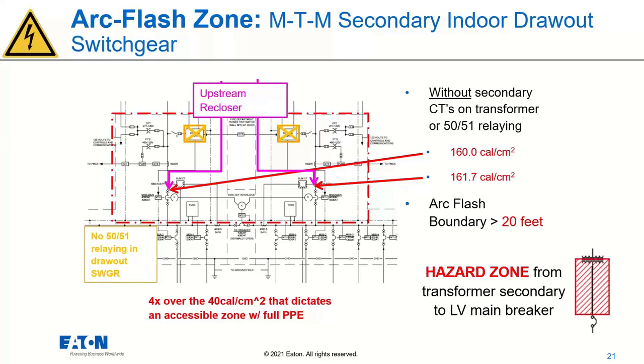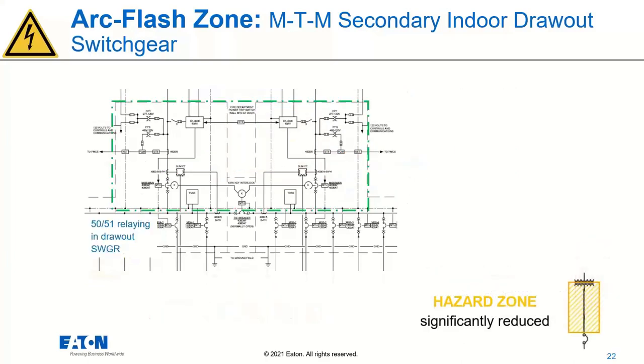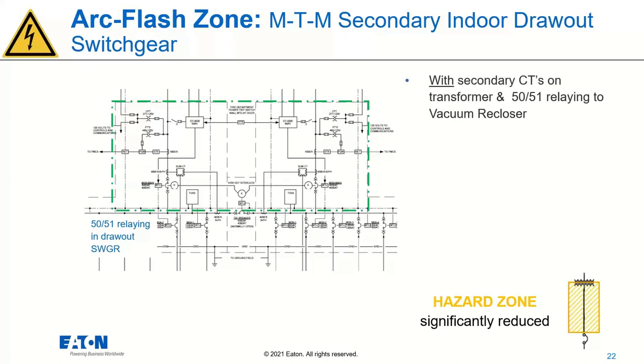And that was a requirement for this customer: they really needed to be able to do hot work. They needed to keep their lines up, and they needed to make sure that this had that always on protection that I was referring to, not something where somebody needed to engage a maintenance mode or something like that. They wanted some way to have this active at all times. That's really going to be that secondary relaying and secondary set of CTs. So a rather simple way to do this is adding those secondary CTs on the transformer and having those feed that 50-51 relay on the secondary, and then have that relay trip that vacuum recloser rather than relying on the vacuum recloser itself and its coordination.